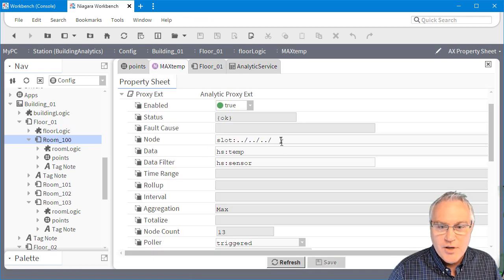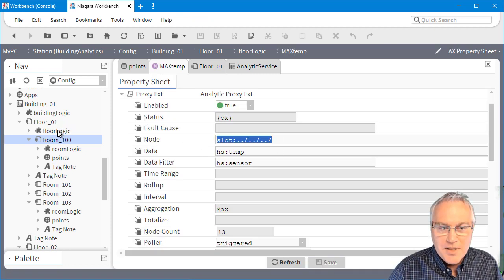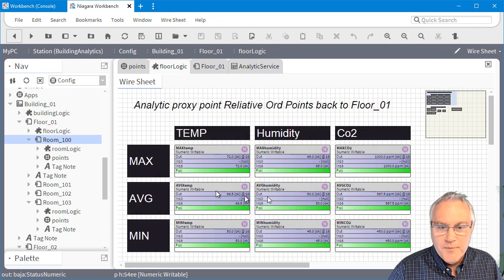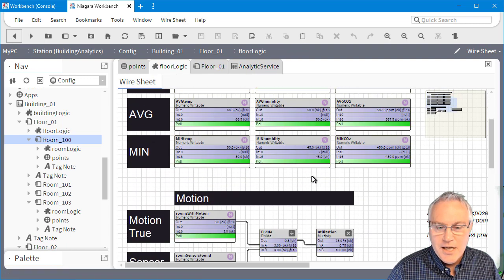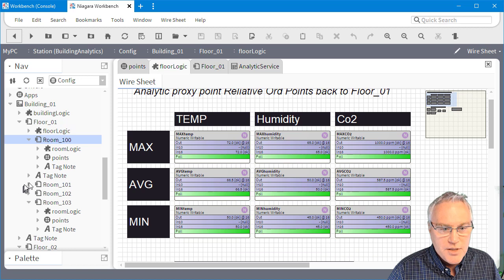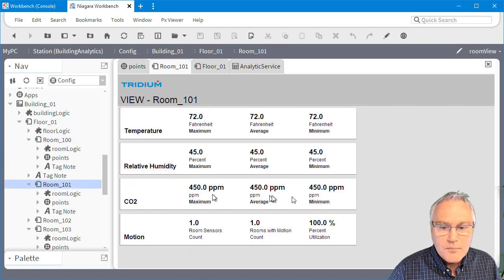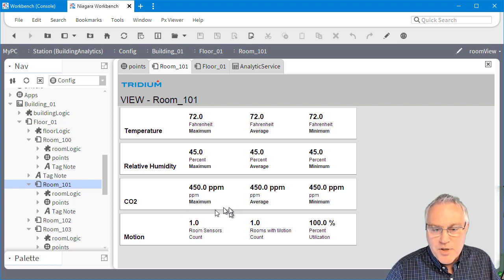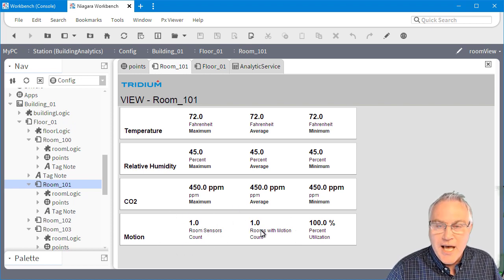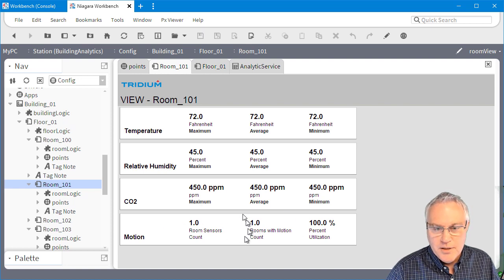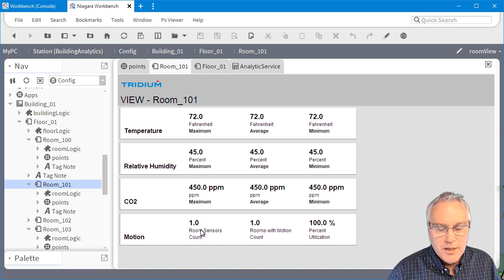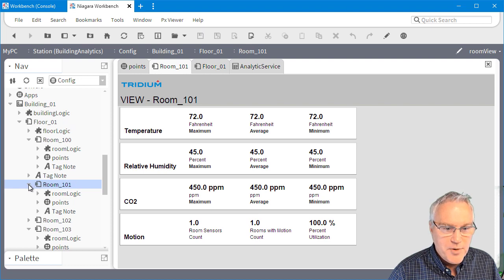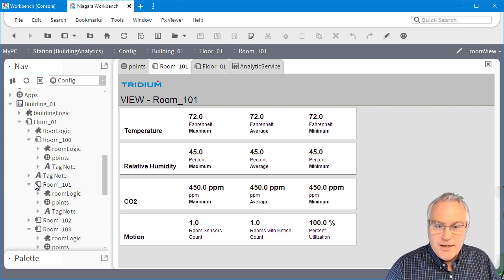But that's how I create these relative ORDs. This is the secret. And applying them in the same structure. And then I can get these that I can cut, copy, and paste in any station that will give me those results. Now, the only thing I will give you the caveat when you get it down into the room, sometimes you'll get some wonky information if you only have one value for it to interpret. So just be aware that sometimes this will give you an odd reading because it tries to sum up those true falses.